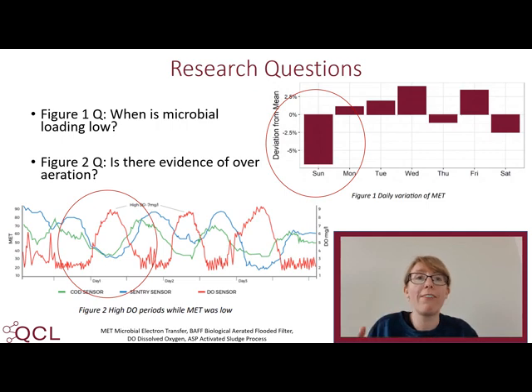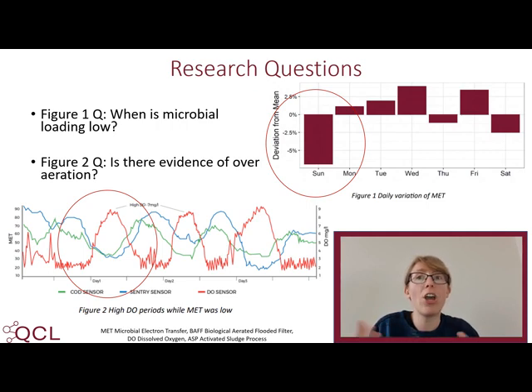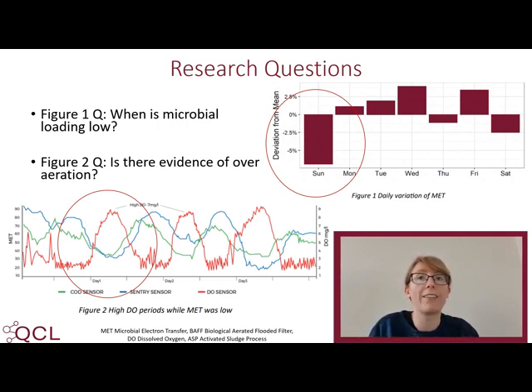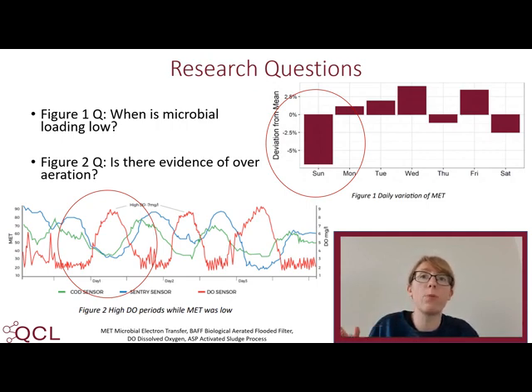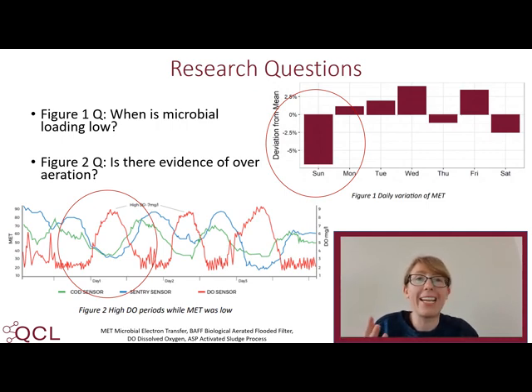We found evidence of over-aeration using the Sentry probes. Figure 2 details how Sentry readings overlaid with on-site dissolved oxygen readings from the activated sludge plant showed that high dissolved oxygen readings correlated with low periods of MET activity, indicating periods of the day where the facility was being over-aerated.